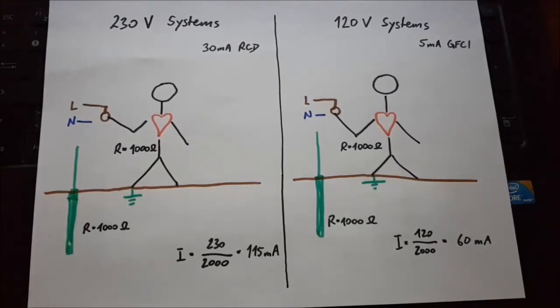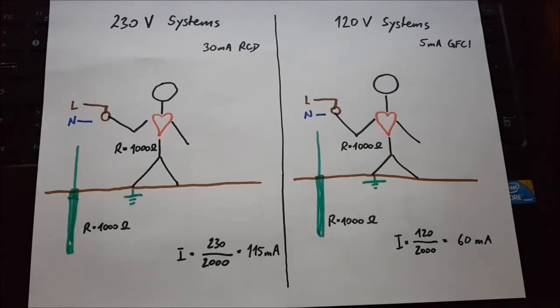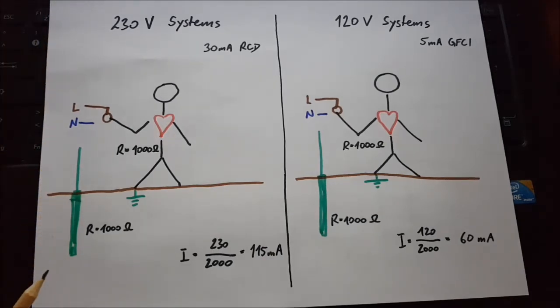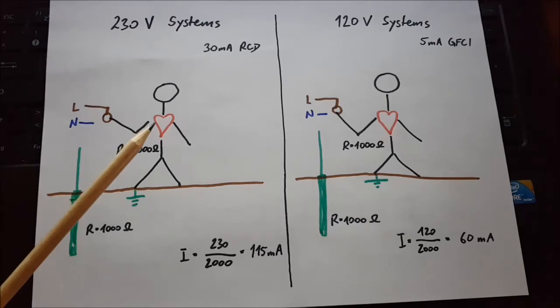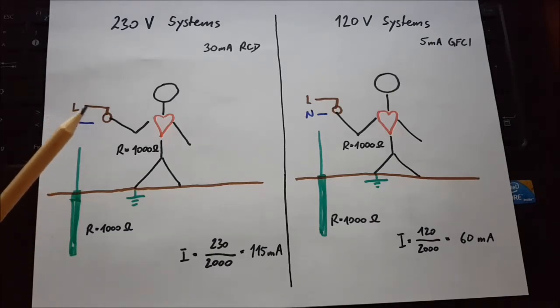So when it comes to protecting a human from getting shocked by a leakage current, it all depends on the design of your protective earth system, of course. And how is that designed usually? We will have somewhere a point of grounding. In a grid setup, this is at the transformer. If we are talking about an off-grid installation, we want to make this at our off-grid inverter. And this is enabling a ground fault loop. So if a human by accident touches a hot wire, current will flow over the human, over the ground, back to the grounding rod of our power source, go into the neutral there, and the circuit is closed. So how does this look in a 230 volt system?